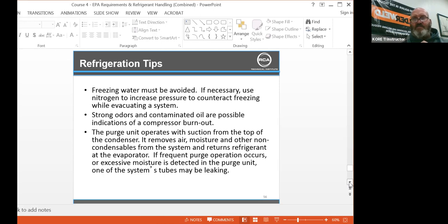The only time I've ever seen purge units is when I did centrifugal chillers. Back in the day, there would be a purge pump on the side of the chiller. If you guys have seen them elsewhere, you can go ahead and unmute and let me know. But centrifugal chillers, not absorption, but centrifugals, recip chillers will have a purge pump. They'll see the non-condensables, they'll come on, condense, and purge the moisture out.